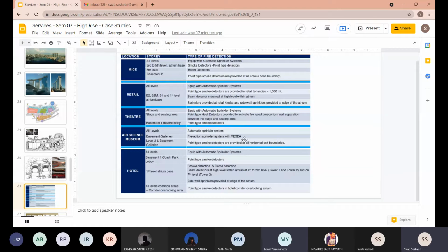So they have employed almost everything. In the atrium, they have side kind of sprinklers. Now the atrium doesn't have a slab, so where would you put sprinklers? When you don't have the slab, how would you assure that firefighting can happen? What they do is use high pressurized sprinklers put on the wall - like the umbrella kind which only falls on half the side. That kind of sprinkler is used, with the limitation that it can fall only to a certain distance, but they are pressurized with a separate line and booster pump setup.